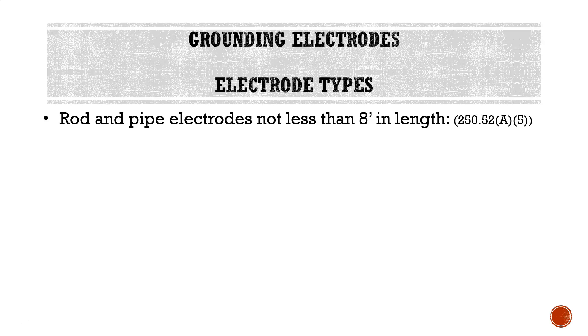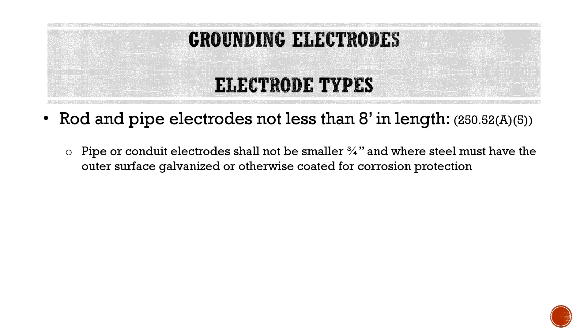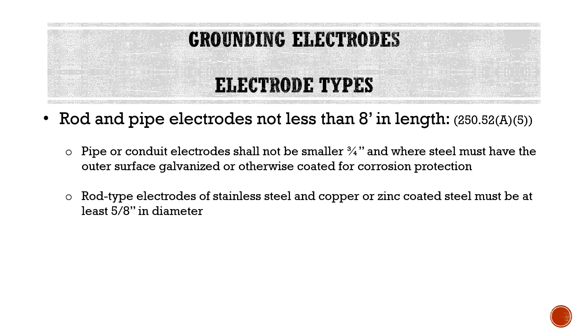A5, our rod and pipe electrodes: not less than 8 feet in length. Pipe or conduit electrodes shall not be smaller than 3/4 of an inch, and where steel, must have the outer surface galvanized or otherwise coated for corrosion protection. So if it's a pipe or conduit, it has to be at least 3/4 inch in size, at least 8 feet long, and have some kind of coating to protect it from corroding. Rod-type electrodes of stainless steel, copper, or zinc-coated steel must be at least 5/8 of an inch in diameter, made or coated with something corrosion-resistant, and at least 8 feet long.